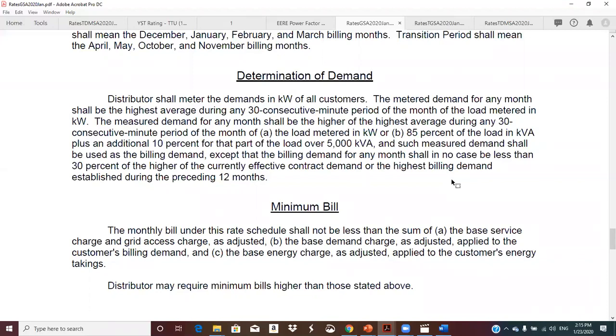If 85% is my threshold, what I'm going to do—because this kW number is constant, really independent of power factor, it's the actual power used by the load—while this kVA number goes up as power factor goes down, is say: this is the number I'm concerned about being too big, so I'll take 85% of it and compare it to kW.